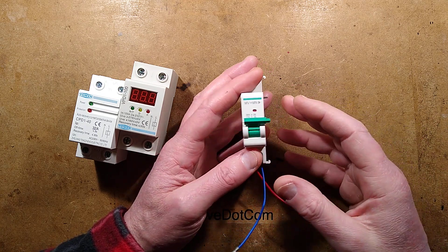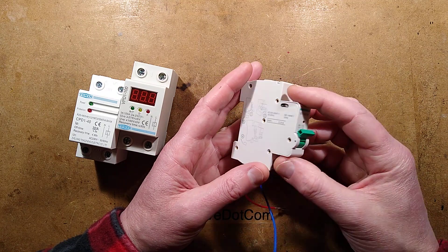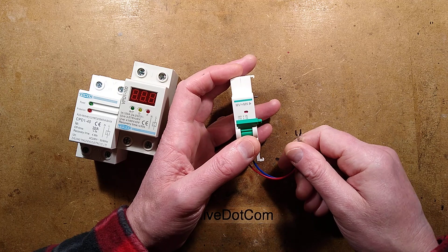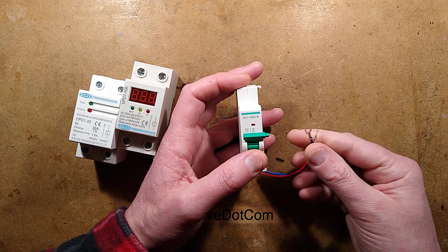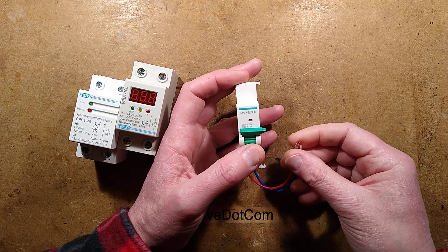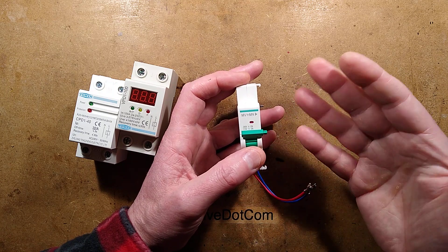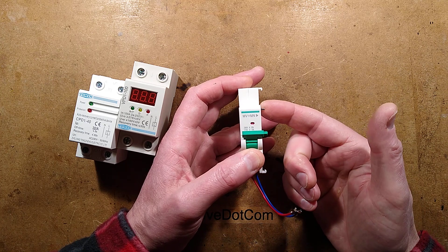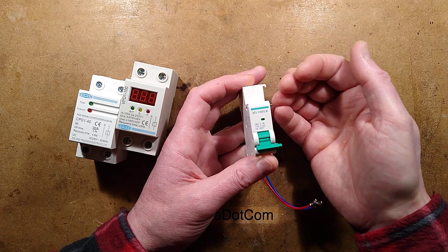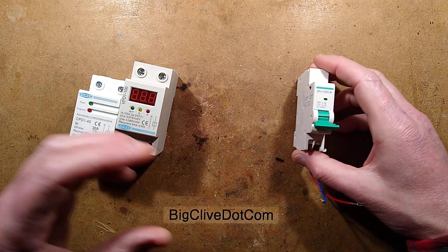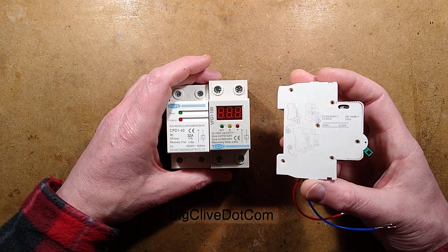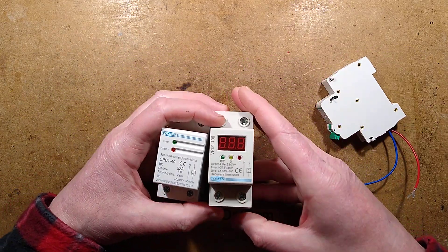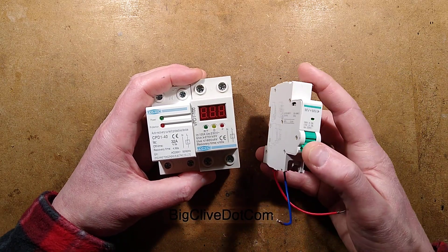It turns out that this is actually an overvoltage/undervoltage trip. This connects to the bottom of the circuit breaker and measures the voltage. If the voltage exceeds a certain margin or goes below a certain margin, it trips off and turns off the circuit breaker next to it.